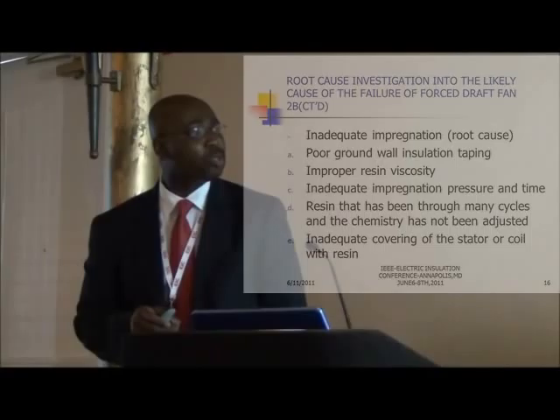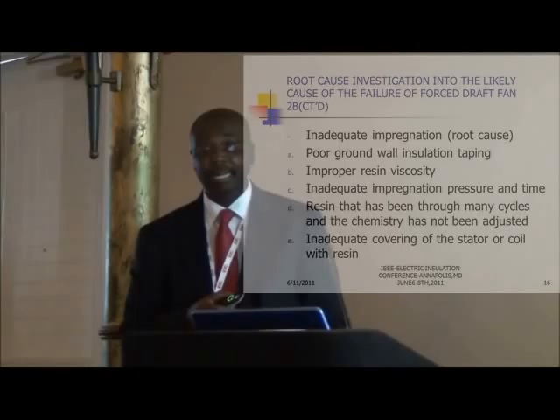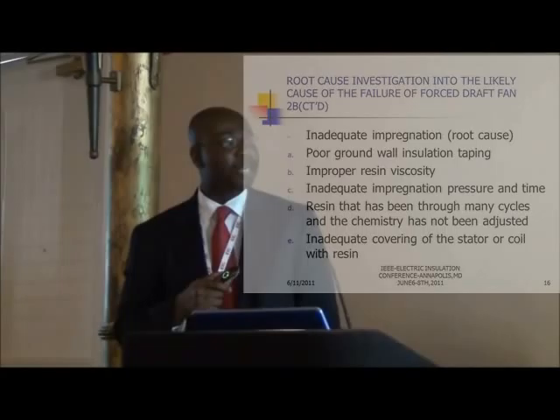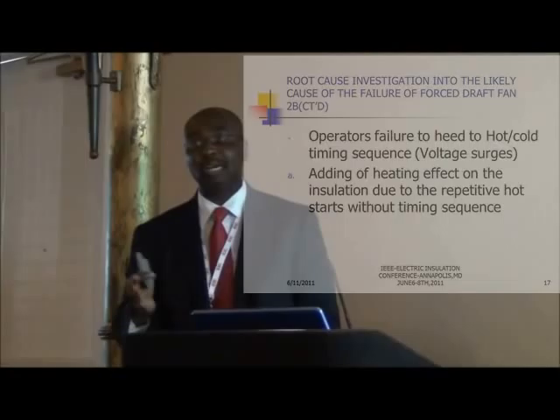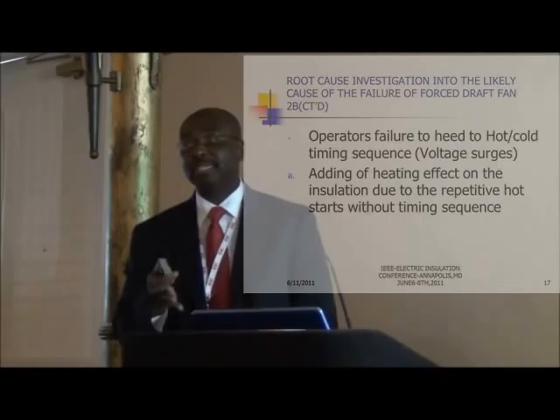The operator's failure to adhere to the cold and hot starting timing sequence can cause significant degradation. In addition to the heat already present, improper starts cause voltage surges. If the insulation is already degraded, those voltage surges can cause further damage. The station also did not have an adequate PM in place to change the filters and clean the motor, leading to contamination and higher temperatures.